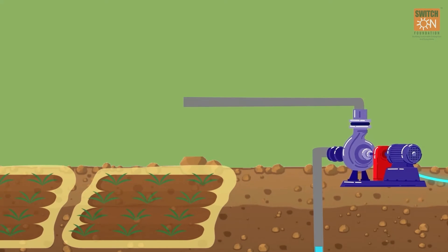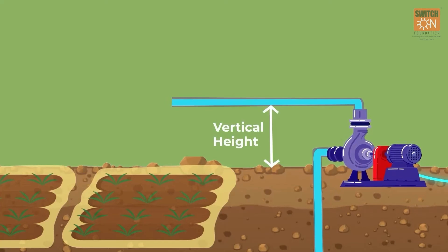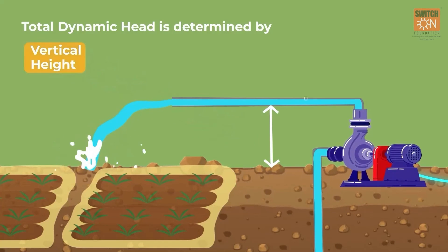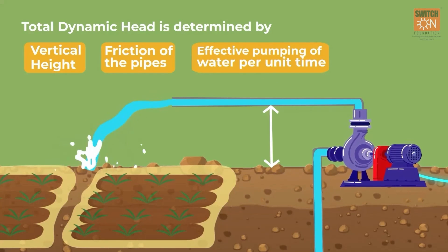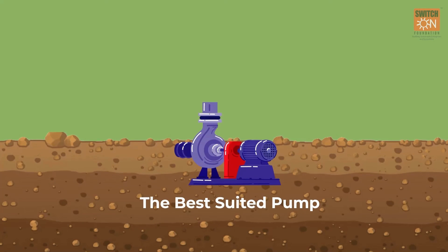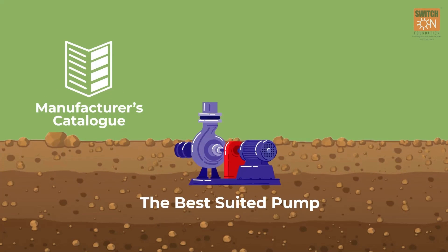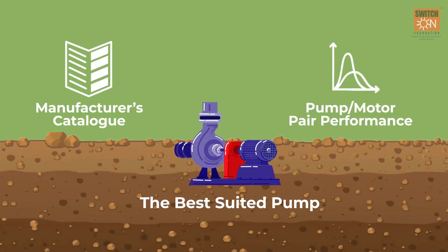The solar water pump is determined by the total dynamic head, which is calculated based on the vertical height that the water must be pumped, friction of the pipes, and the effective pumping of water per unit time. The best suited pump is decided based on manufacturer's catalogues and pump-motor pair performance curves, to ensure that the pump-motor pair can deliver the required water flow against the total dynamic head.